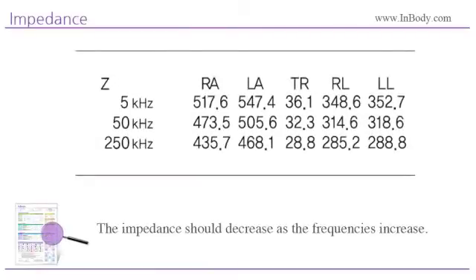Impedance. Check to see if the impedance value decreases as the frequencies increase. If the impedance values do not decrease, this means that the measurement was not taken correctly. Please take the measurement again.